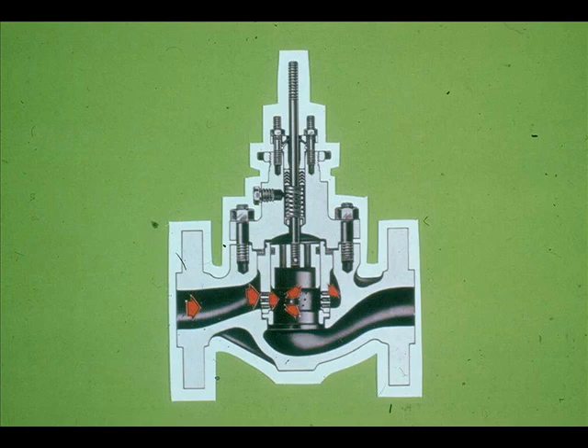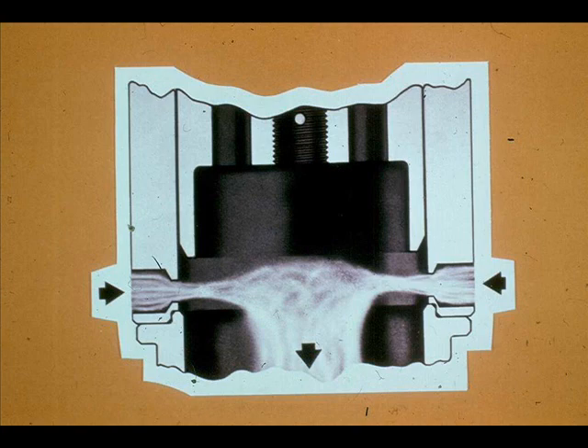The fluid flows through small holes in the plug, and the fluid reaches maximum velocity. Voids or bubbles form in this area. Then the fluid enters the hollow plug area. Velocity rapidly decreases in the hollow area of the plug. Pressure is recovered, causing the bubbles and voids to implode. Since the implosions are inside the hollow plug, no damage is sustained to the trim.